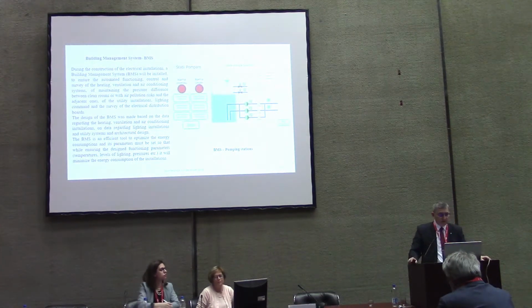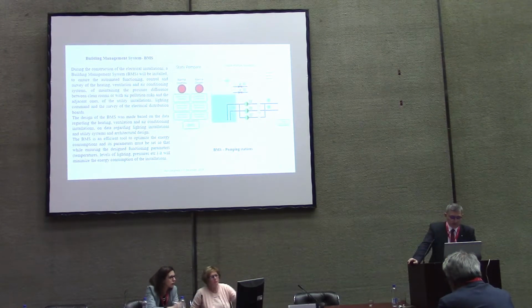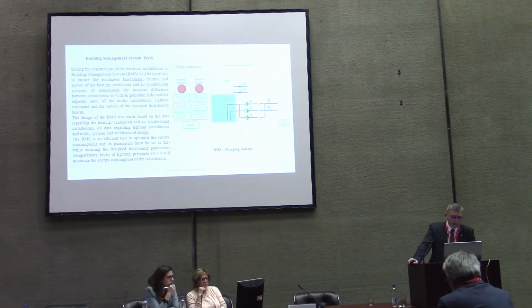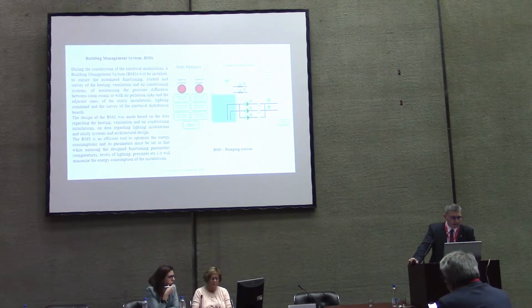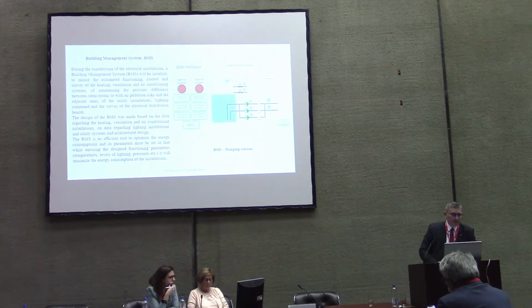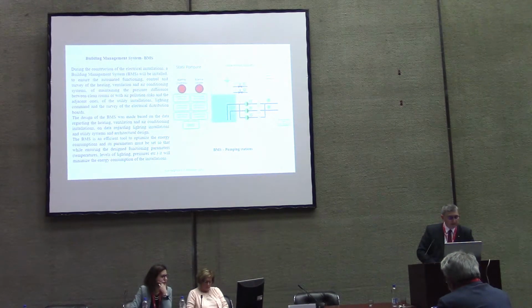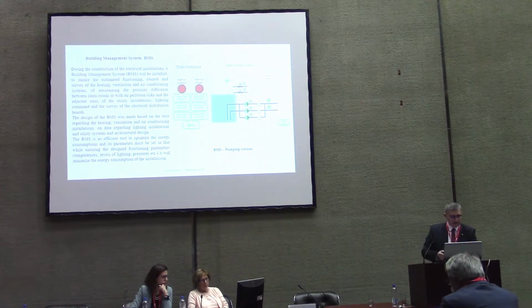The building management system is one of the most important parts of building services, because the energy performance of the building was a goal for this hospital, and we can achieve that through the building management system. That will be installed to ensure the automated functioning, control and survey of heating, ventilation and air conditioning systems, of maintaining the pressure difference between clean rooms with air pollution risk and adjacent zones, of the utility installation, lighting command and the survey of electrical distribution.